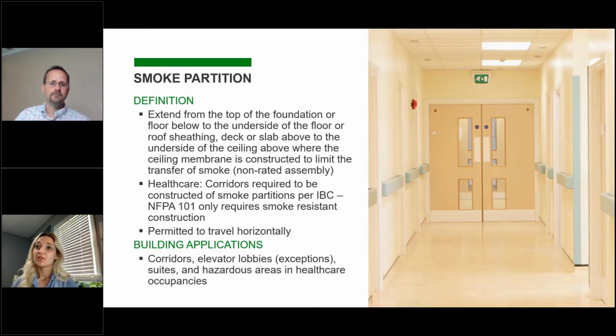All right, so we are almost at the end of our list of the least hardy of these rated constructions. So, a smoke partition. I'll note right off the bat that a smoke partition in IBC is a term that's typically used for healthcare occupancies, and NFPA 101 calls for smoke resistant construction in corridors. And the key point for smoke partitions is that it's a non-rated assembly, so there's no fire rating associated with it. It can terminate at a ceiling that is constructed to limit the transfer of smoke. So in most cases, you'll see this won't be a rated assembly for the ceiling, but the smoke partition is permitted to terminate at that ceiling. So it'll go from the floor to the ceiling or the deck above, depending on how the ceiling is constructed.